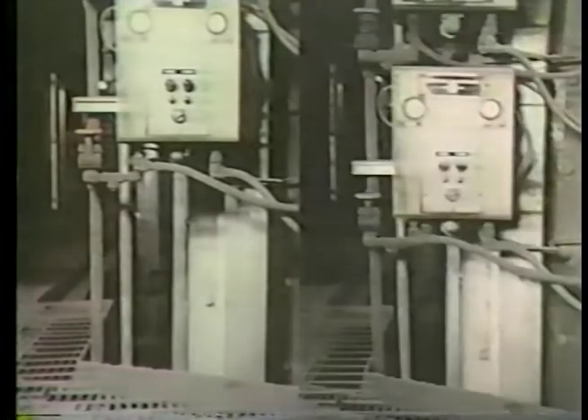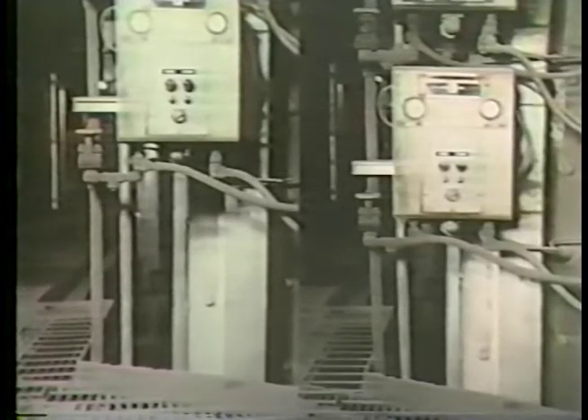When a boiler is first started up, the temperature of its metal components increases. Here, for example, is an igniter control box on the side of a cool boiler. Here is the same box after the boiler has been operating several hours. Notice the difference in the height of the box in relation to the floor. The increase in temperature causes the boiler to literally stretch. It is not unusual for the overall length of a boiler to increase as much as 12 inches during startup.